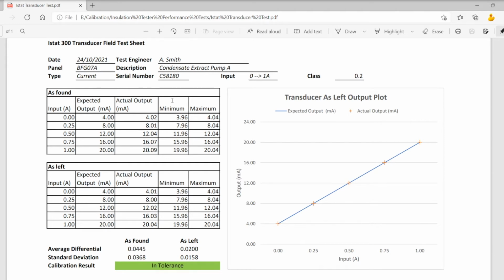And you can see here, this is the as found. You saw when I tested it earlier in the video that it was actually out, 20.09. Max I can have is 20.04. Again, 16 milliamp was out as well. So the span needed a little bit of adjustment. Once I've adjusted it, I can bring it back down into tolerance, and these are my as left readings, and I give them an overall result that the unit has been left in tolerance, and there's my little output plot there, and I do that for each transducer that I tested.